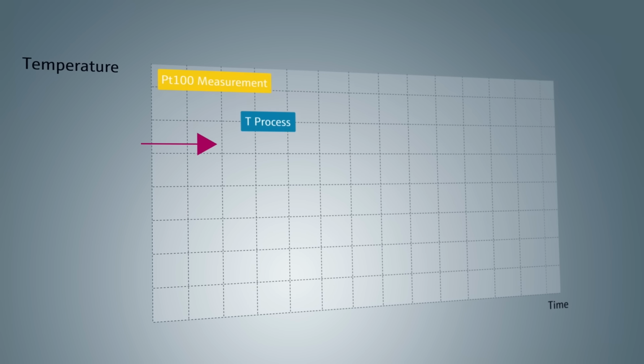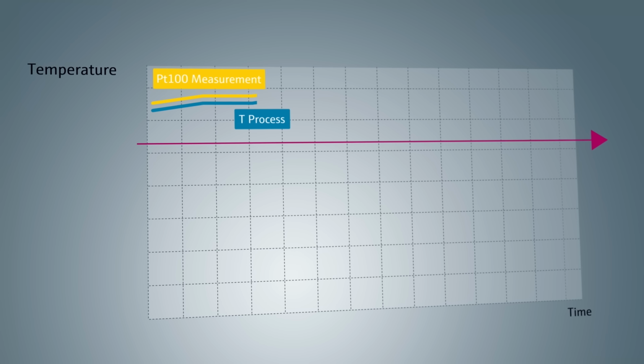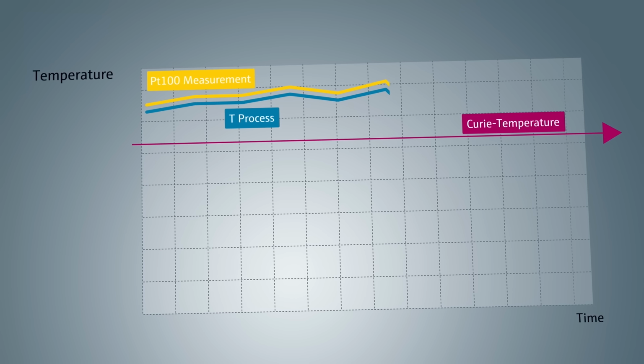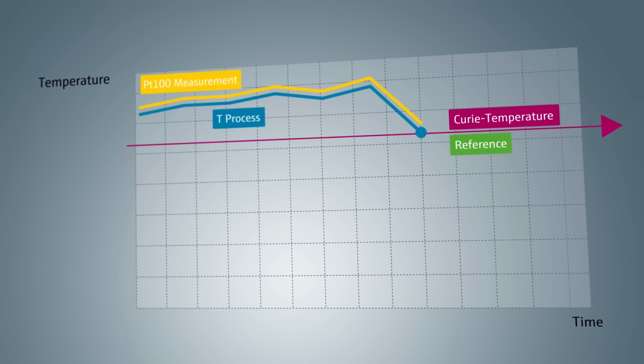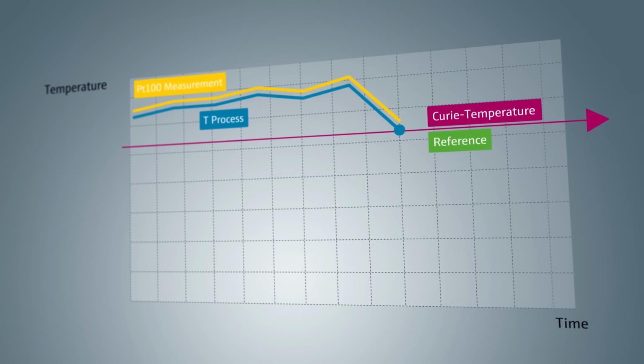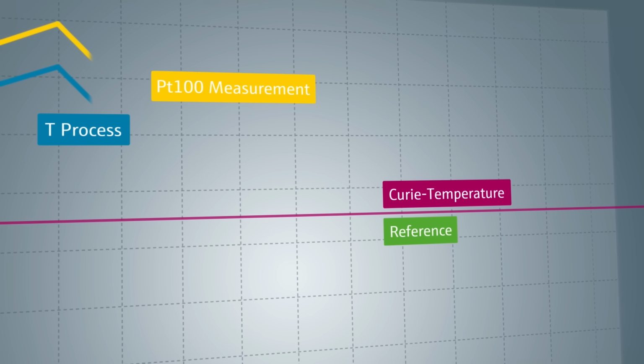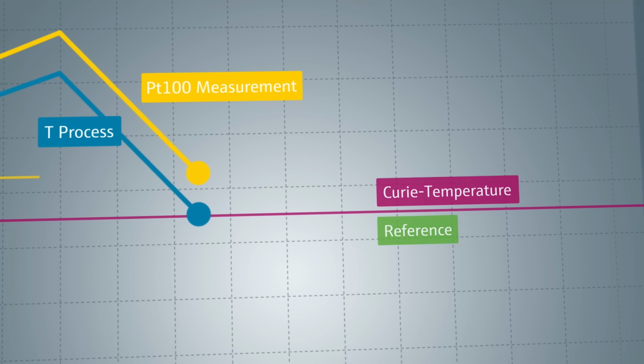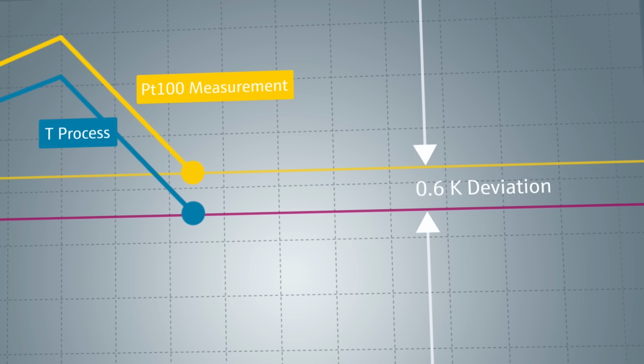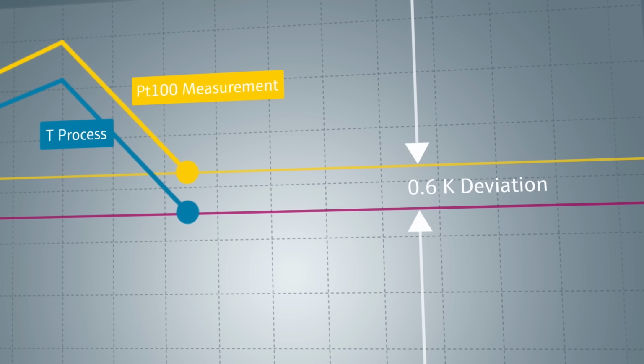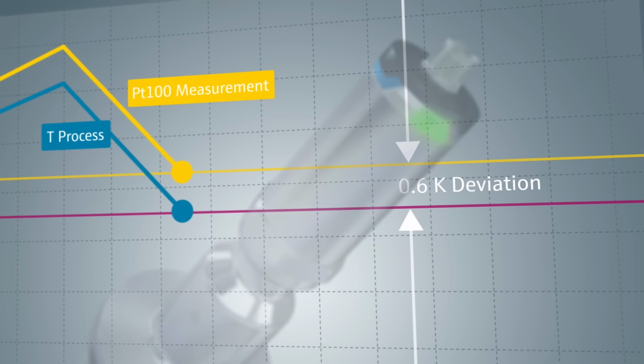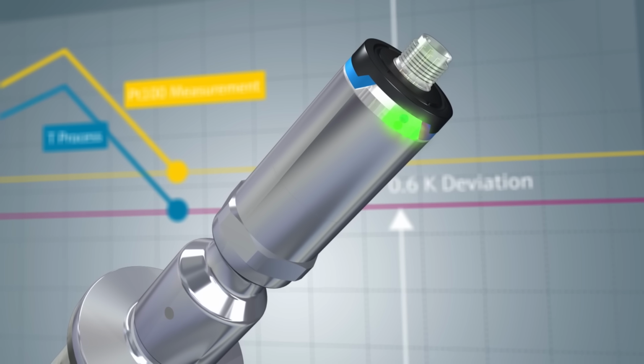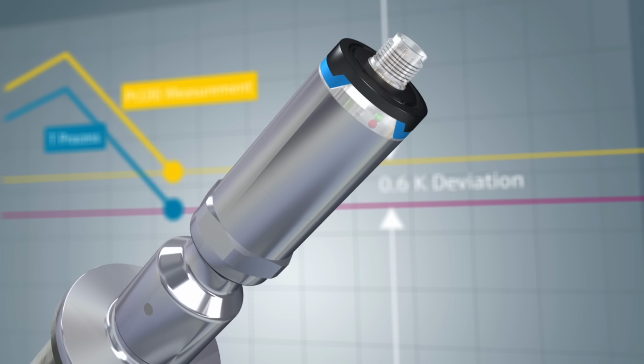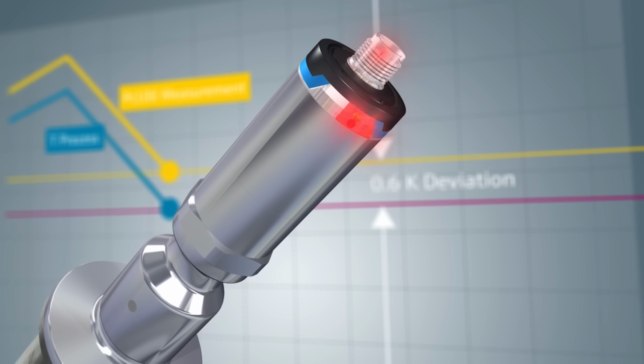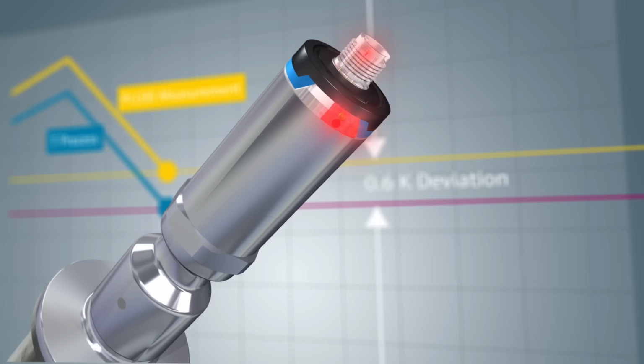Once the Curie temperature is reached, the reference sensor transmits an electrical signal. At the same time, a measurement is carried out in parallel via the temperature sensor. Comparison between these two values is effectively a calibration that identifies any measured errors with the PT100. If the measured deviation is outside of the set limits, the device issues an alarm or error message that is also displayed on-site via LED.